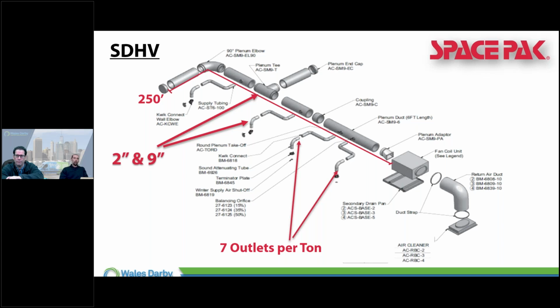But if I know I'm doing a 3-ton system, we can do some simple math and say it's going to be 21 outlets total. That might be a good way to budget a system, but we need to do a design - you need to know how many BTUs. Unlike traditional, where we're trying to figure out CFMs and all this air delivery, that's one portion you can save some time with as far as design, by understanding how we size our rooms based on BTUs, how much air we have to deliver.